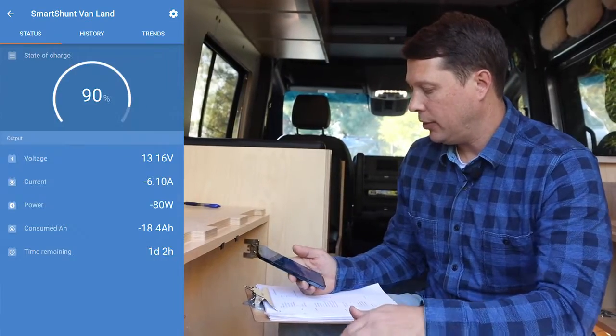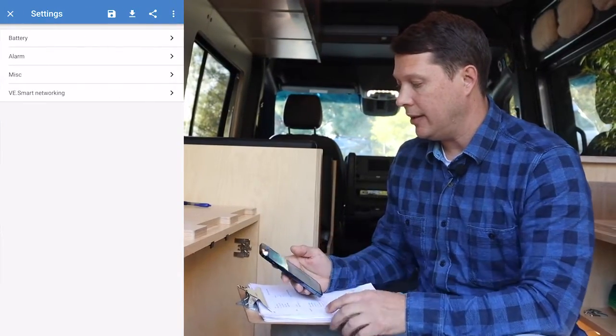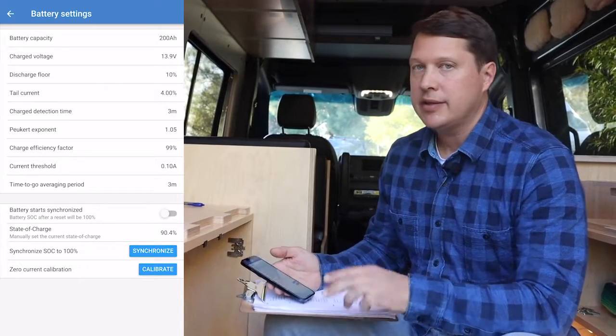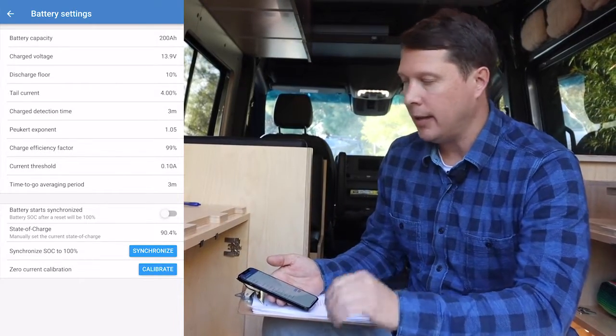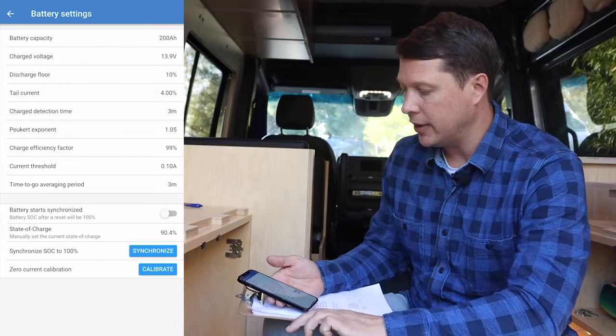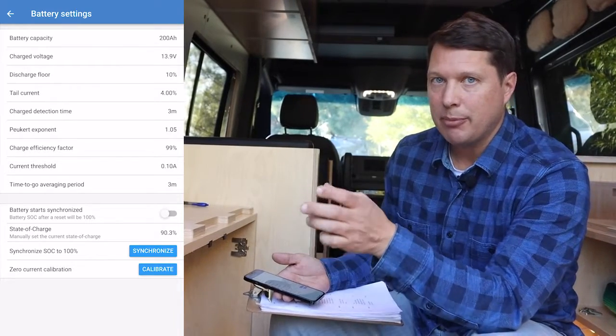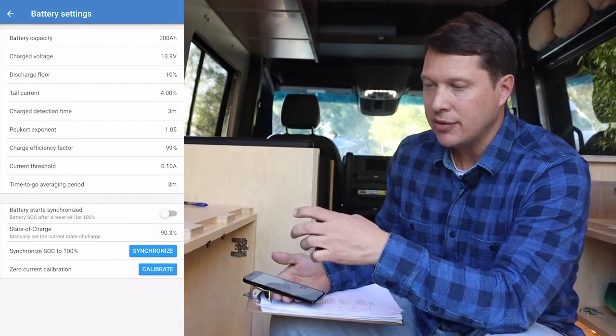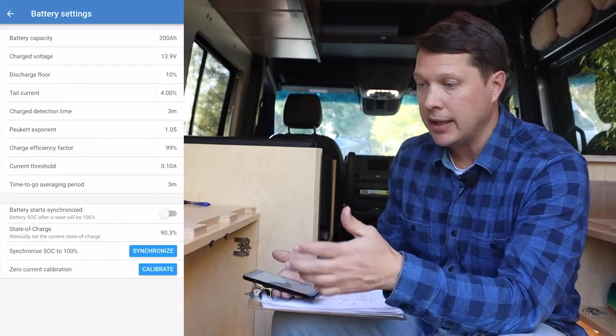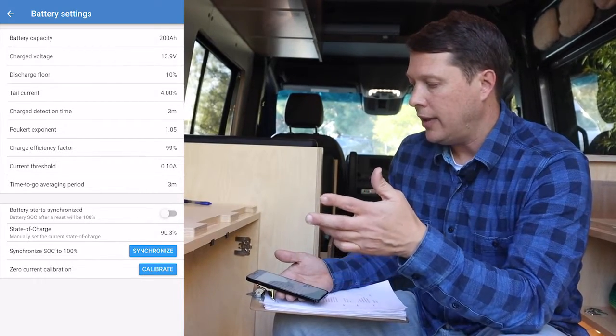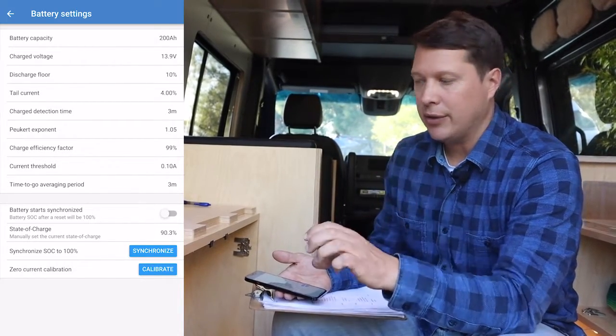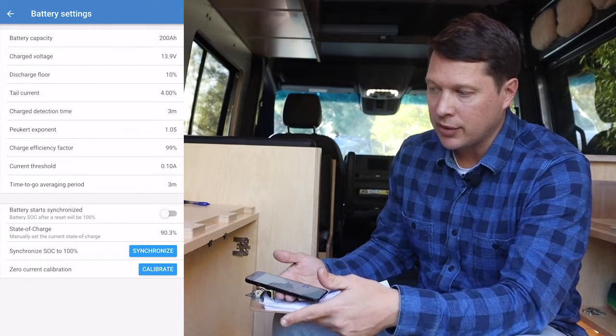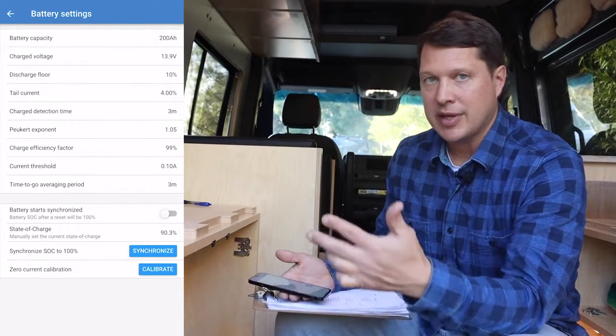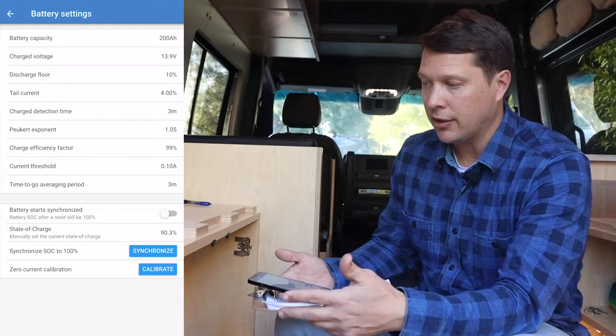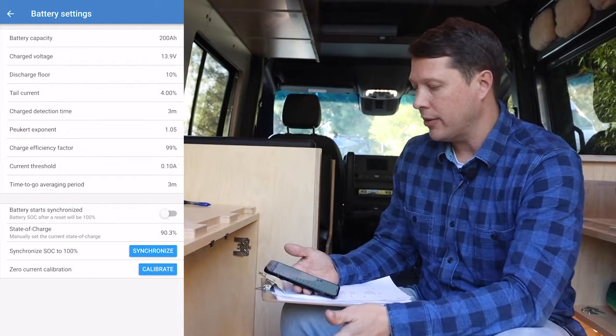And the first thing that we're gonna need to set is the battery settings, to tell the smart shunt how many amp hours of battery storage that we have here. So the shunt's purpose is to measure the flow of current in and out of the battery system. And that is how we actually get the calculation that tells us what percentage of battery we have left and how much time we would have left at our current amp draw with the battery power that we have.